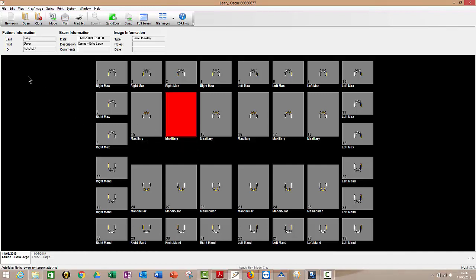Obviously, it doesn't matter how many you leave empty. That doesn't matter at all. And so you just take as many images as you want to, and then they'll automatically save. So as soon as you can see the images on screen, they're saved. So that's how you take images. And as long as you remember to click the right box before you start. So this is dental right and dental left. So in other words, the left of the screen is right and the right of the screen is left. It's as if the animal's looking out at you. As long as you remember to click the right box first, then the image will always be in the right orientation, the right way around. It won't be upside down. It won't be back to front. If you forget to do that, I'll show you how to correct that in a minute. So that's how you set up for a new series of x-rays.